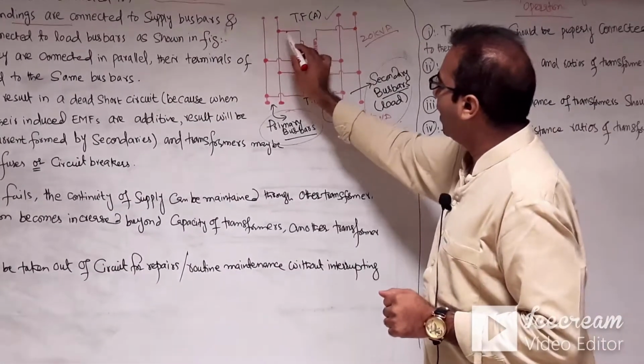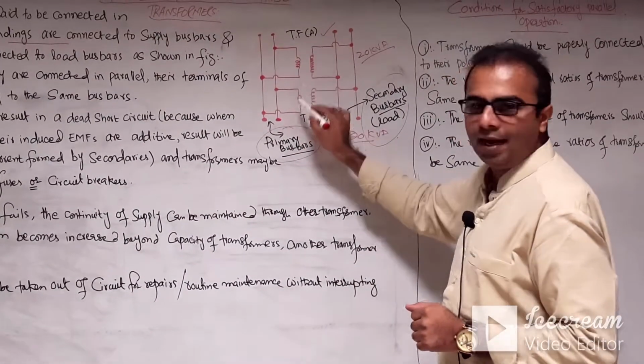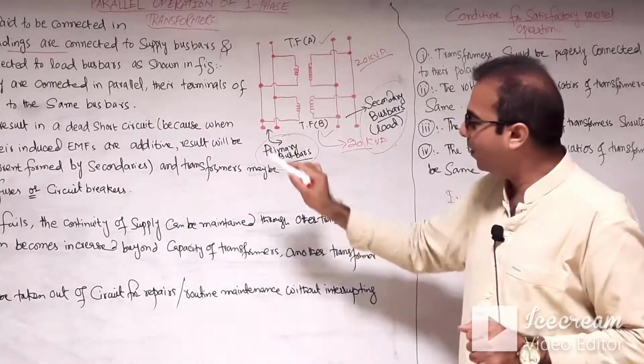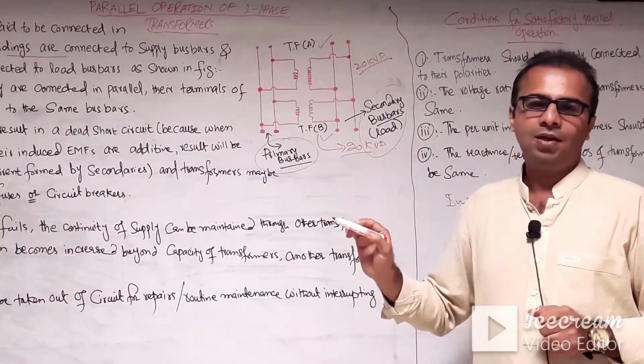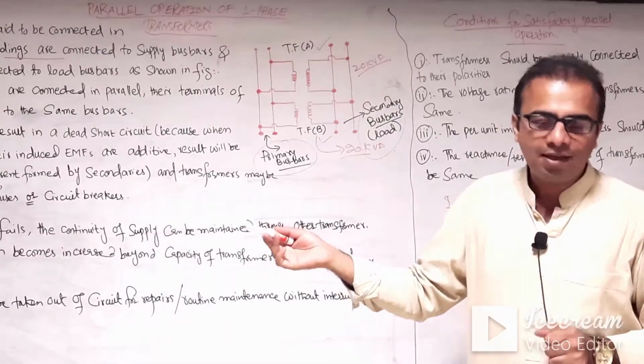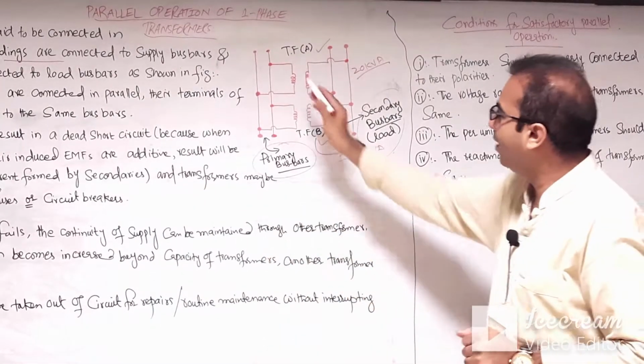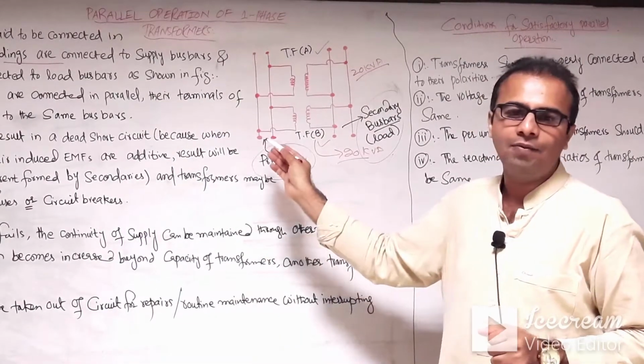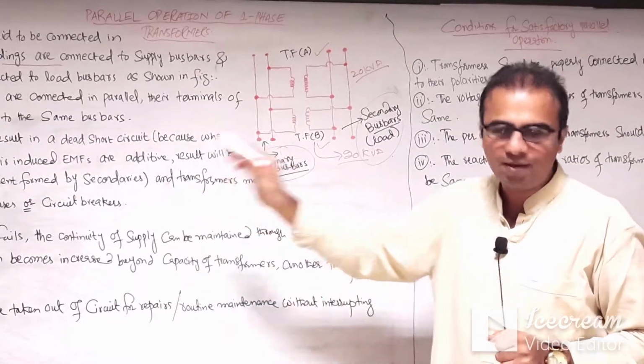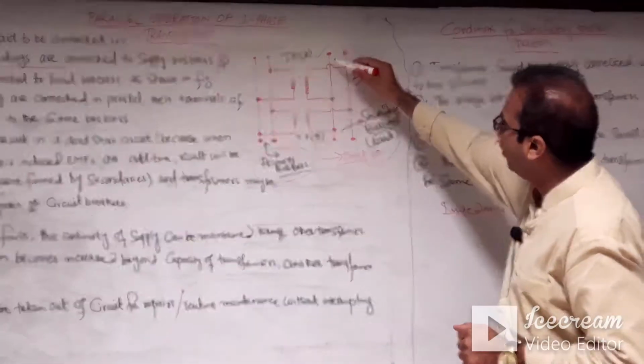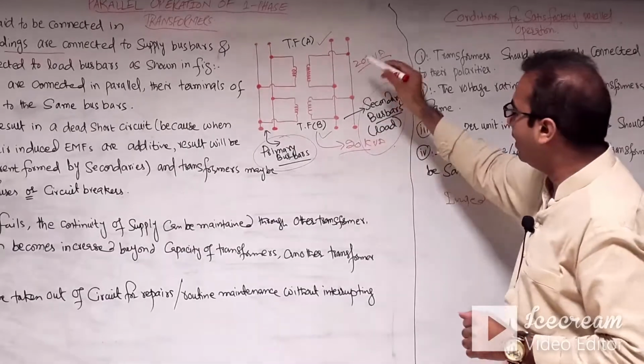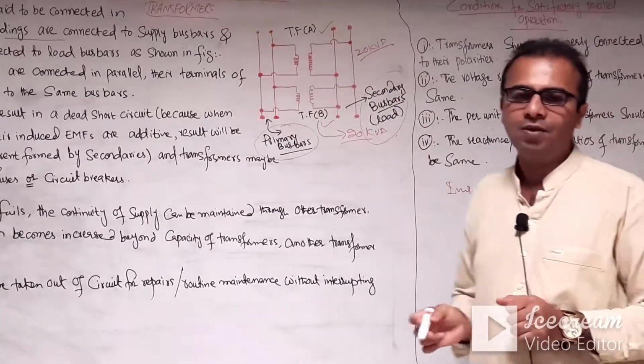The primary windings of both transformers A and B are connected with the supply bus bars. These are the supply bus bars. Another name for the supply bus bars here is the primary bus bars. Primary windings of both transformers are connected with the supply bus bars or primary bus bars. And the secondary windings of both transformers A and B are connected with the secondary side bus bars or the load bus bars.